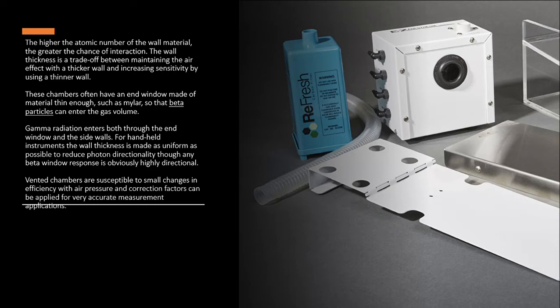The higher the atomic number of the wall material, the greater the chance of interaction. The wall thickness is a trade-off between maintaining the air equivalence with a thicker wall and increasing sensitivity by using a thinner wall. These chambers often have an end window made of material thin enough, such as Mylar, so that beta particles can enter the gas volume. Gamma radiation enters both through the end window and the side walls.